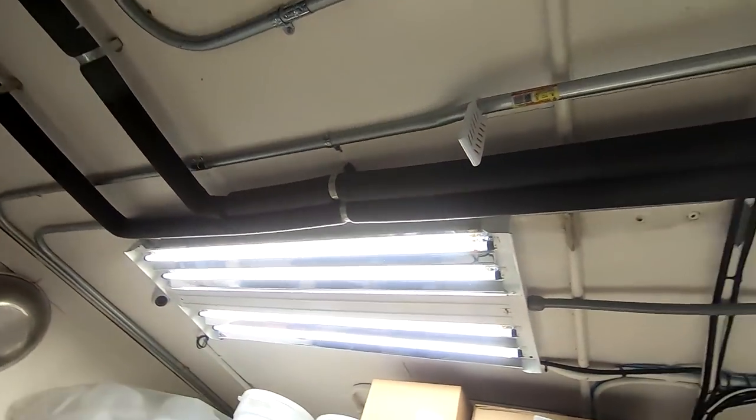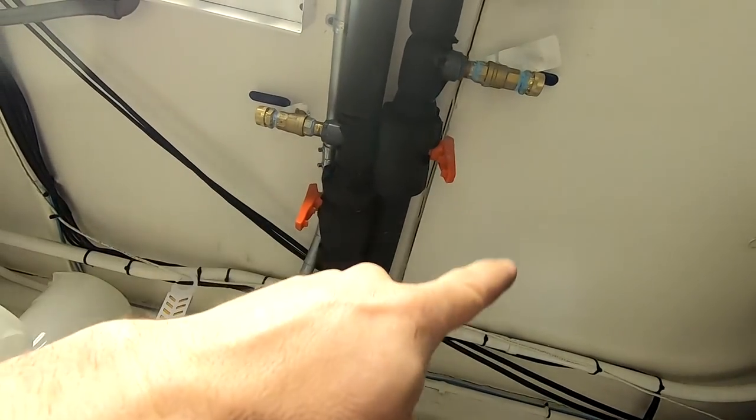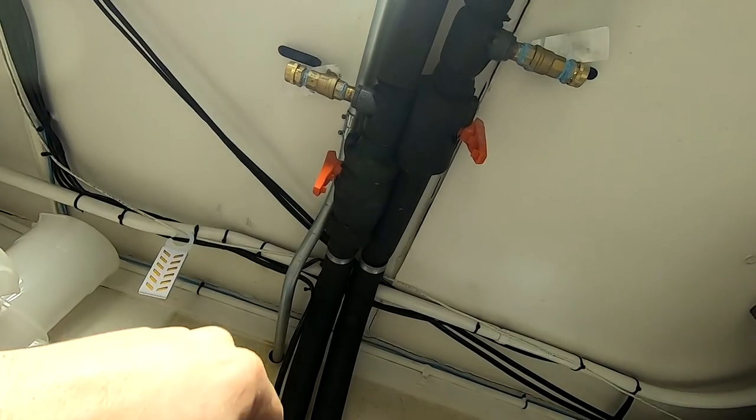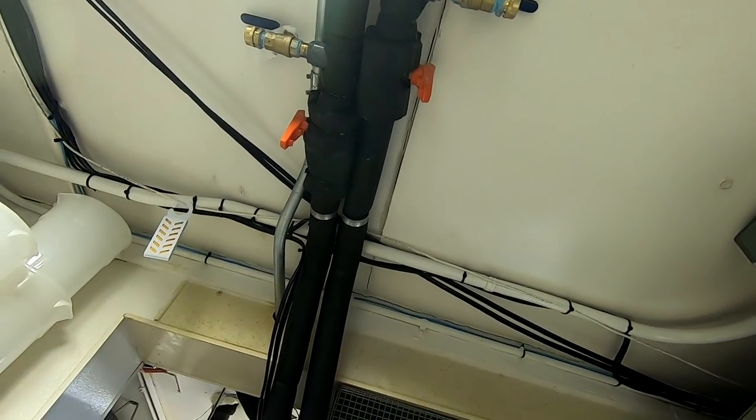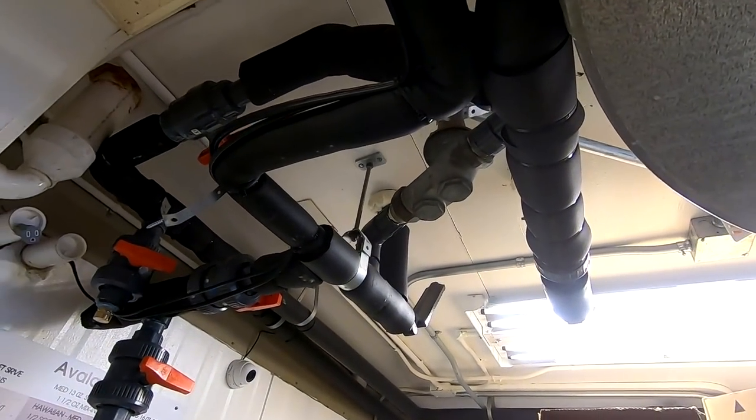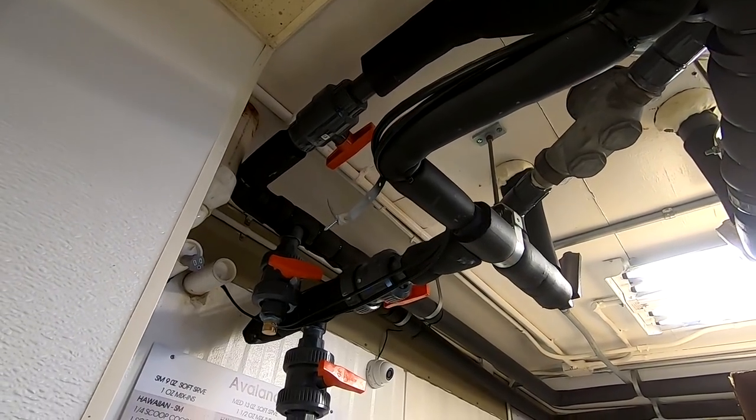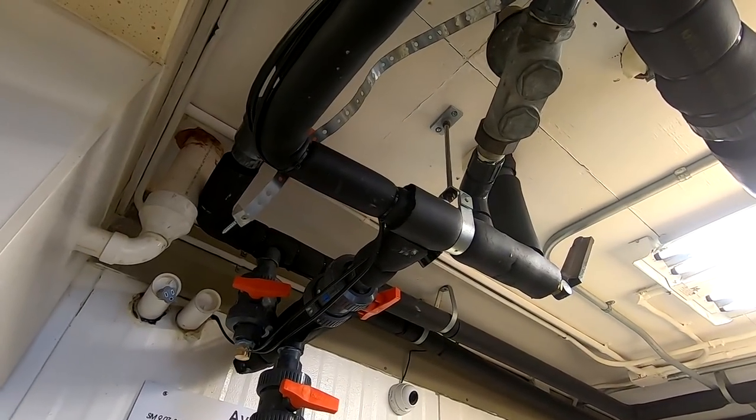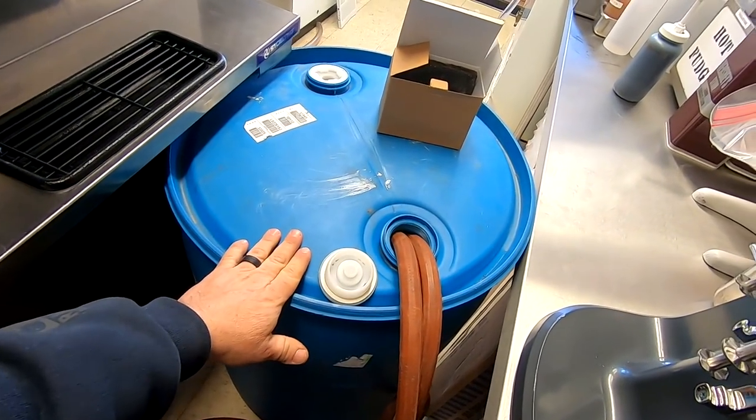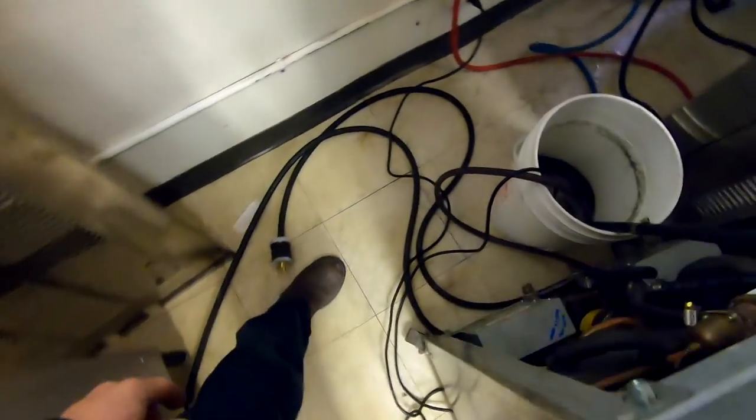And when we have to work on them we've got, like I said, two ball valves here and ball valves to isolate it so we can actually bleed these one at a time. With a parallel circuit that we have going on here, it was very difficult to get all the air out. It was just a nuisance - didn't happen very often, but when you do have an issue it really sucks. We basically reclaimed our glycol and we'll be pumping that back into it, so we're going to go ahead and put this thing back together.